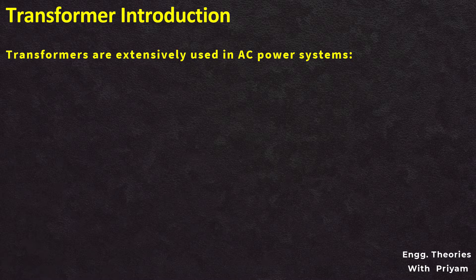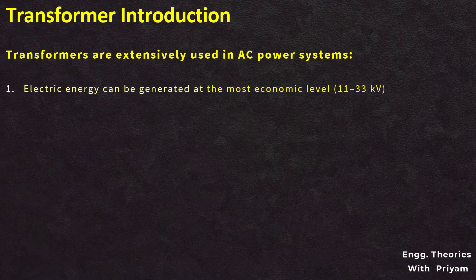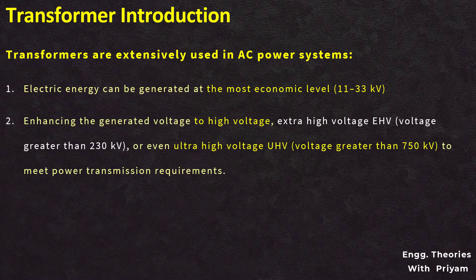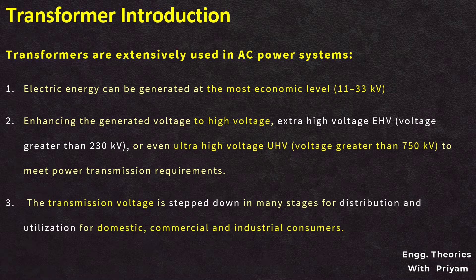Transformers can immediately step up the voltage at the side of power generation before transmission and distribution takes place. They are extensively used in power systems because electrical energy can be generated at the most economic level — from 11 to 33 kilovolts — and then the generated voltage is enhanced to extra high voltage (EHV, greater than 230 kV) or even ultra-high voltage (UHV, greater than 750 kV) to meet power transmission requirements, reducing losses and enhancing transmission capacity.